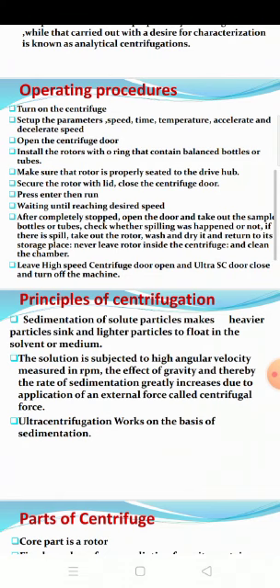Check whether spillage has happened or not. If there is a spill, take out the rotor, wash and dry it, and return it to its storage place. Never leave the rotor inside the centrifuge, and clean the chamber. Leave the high speed centrifuge door open, close the ultracentrifuge door, and turn off the machine.